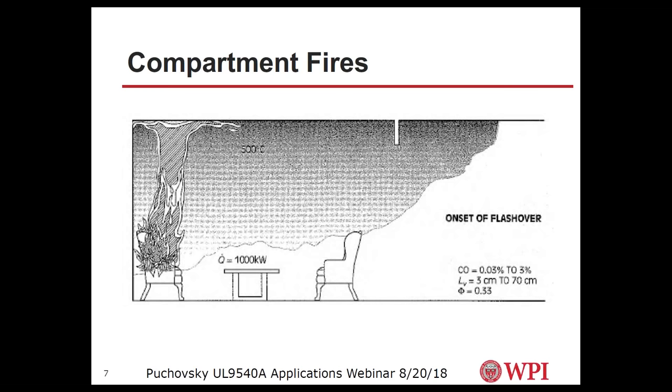However, what may happen at some point because of the smoldering combustion that occurs is once somebody comes to that room and opens up another vent, you could have something like a backdraft effect, a deflagration type effect, because now all of a sudden, all those gases that were produced and were lacking oxygen, there's sufficient heat in that particular compartment. Now you've allowed for sufficient oxygen to come into that room, and now you can get a very substantial fire effect that may create substantial pressures and get into the range of an explosion.